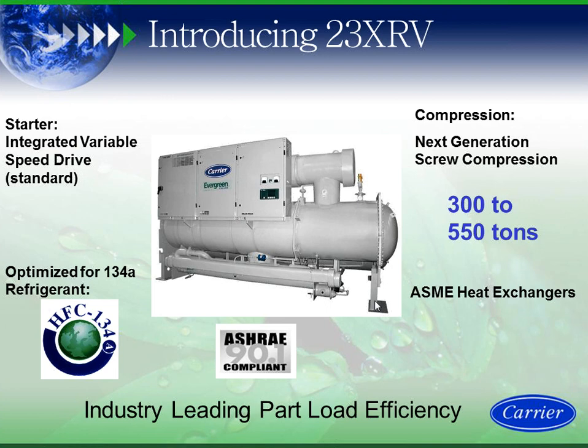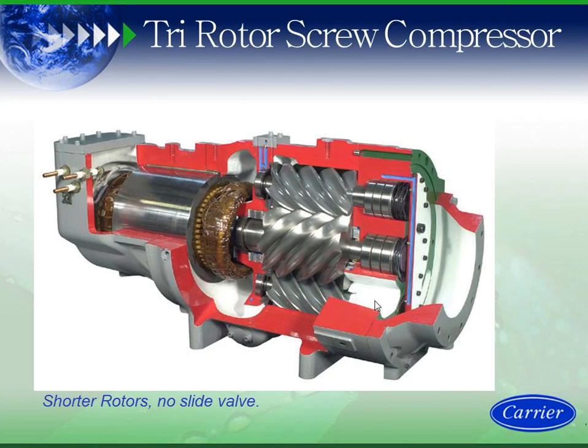ASME pressure vessel, and we have the next generation tri-rotor screw compressor. So that's what we're designing, and all our chiller plant energy analysis pieces are going to be designed and optimized around the 23XRV screw chiller. This is a picture of the screw chiller. It is extremely robust. It's basically, I've got shorter rotors. It's not like a twin rotor machine. I have shorter rotors. It has no slide valve.